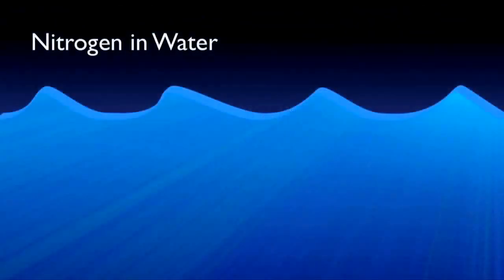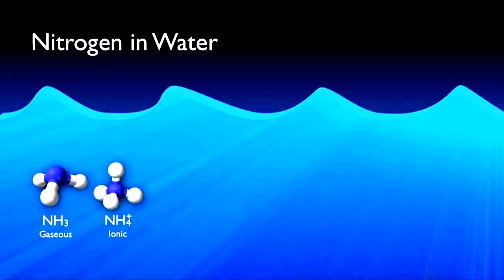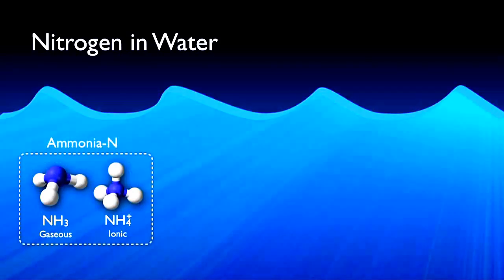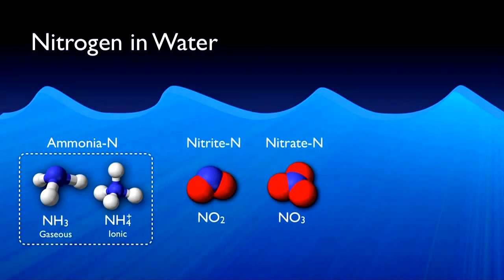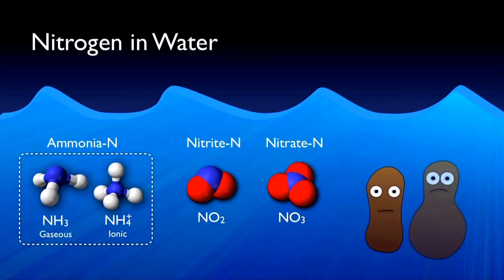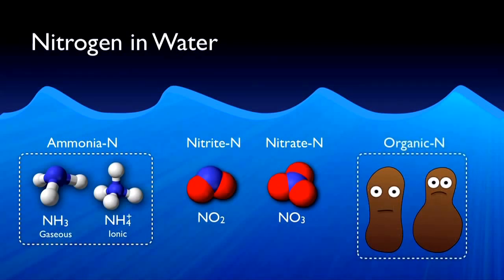Nitrogen is present in wastewater in various forms which have been lumped into separate general categories. Nitrogen in the form of ammonia is ammonia nitrogen. There is also nitrite nitrogen and nitrate nitrogen, which are usually formed during the actual biological processes at the wastewater treatment plant. In addition to these forms, nitrogen makes up a small percentage of the cell mass of organisms in the system, as well as other dissolved organic compounds. This category is referred to as organic nitrogen.